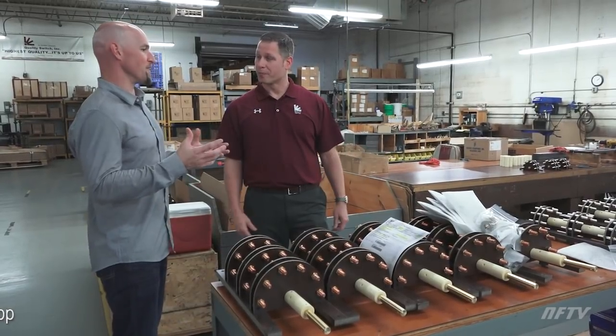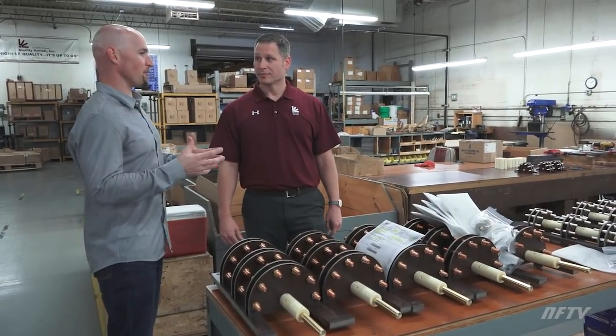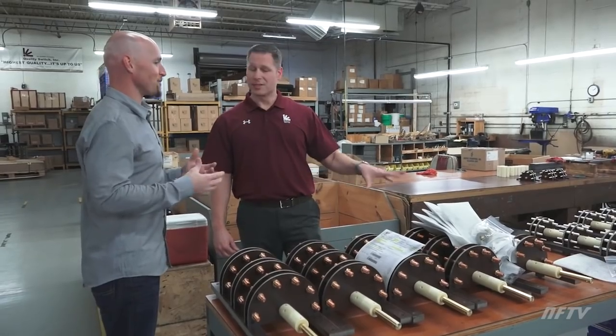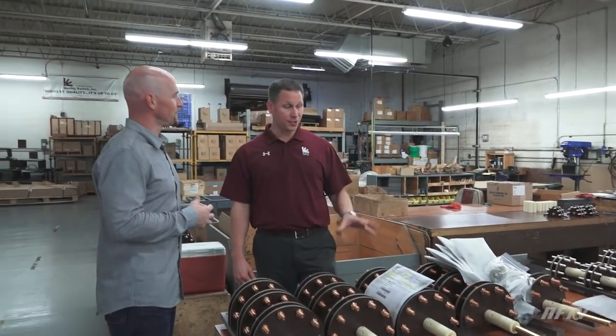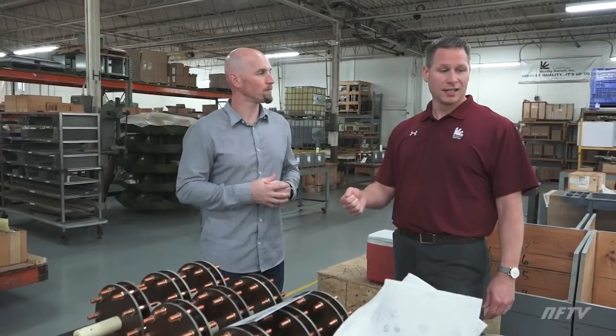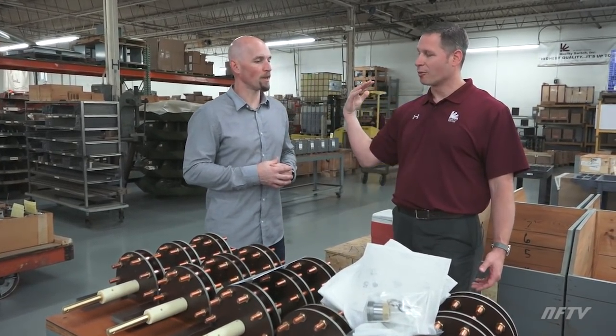People see these every day and don't even realize they're there, because they're inside that product. They're basically used for voltage regulation. If somebody wants 120 volts or 110 volts coming out of their light socket, the transformer steps the voltage down from the grid, and there's some fluctuation based on the line runs, so the switch allows it to regulate that flow.